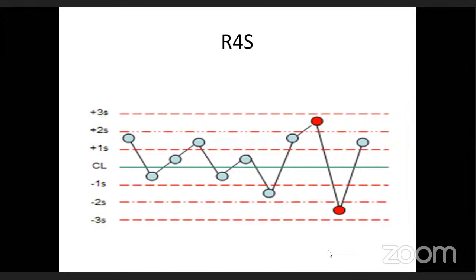So what are the corrective actions that you're supposed to do? First of all, you need to make sure that your reagent is not deteriorated. You must look at your reagent, whether its shelf life has been exceeded or not. Secondly, you will look at your calibrators: when was the last calibration done? Was it successful or not successful?